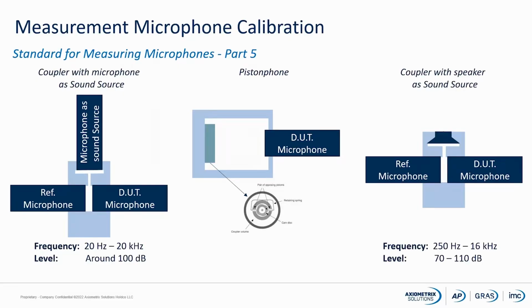With a piston phone, you do have a volume. It's the one we have here. Then we have two pistons, and these two pistons will actually move, because a little motor makes them move. When they move up and down, the pressure inside the chamber will be built up, so you will have a certain pressure inside the chamber. This is a fixed frequency, normally 250 Hertz, and a fixed level, 94 dB, 114 dB, or 134 dB in this neighborhood.